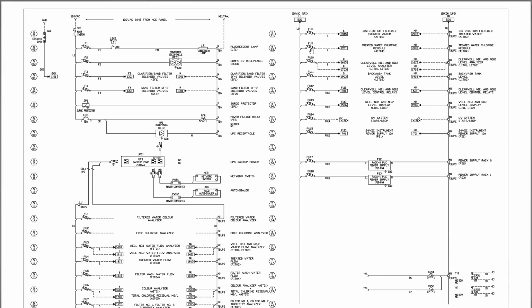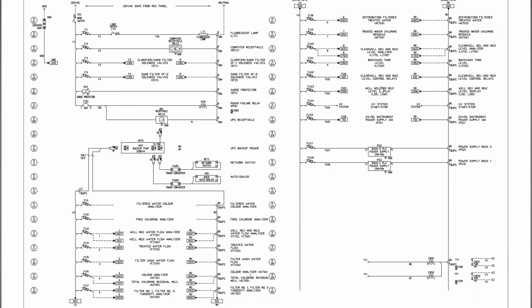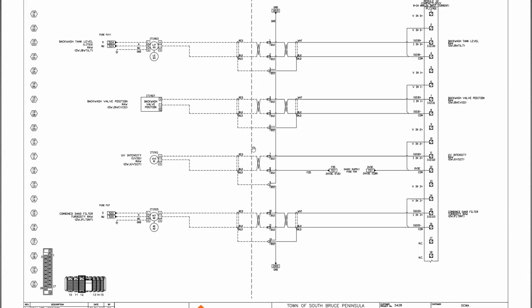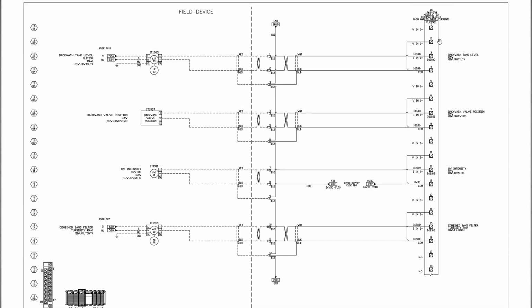6, 7. You can see all these fuses again, going out to their devices. And if we move through, we'll find where those instruments are elsewhere in the drawing set. They look like they're all on IO drawings. Again, here, backwash tank level. It's on 1903. So if we fly to page 1903, we have another analog input from a backwash tank level. The instrument itself receives 120 volt power. And then this is the 4 to 20 circuit for its analog signal into the PLC.